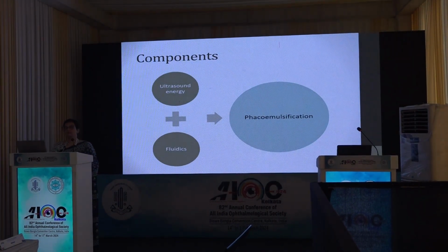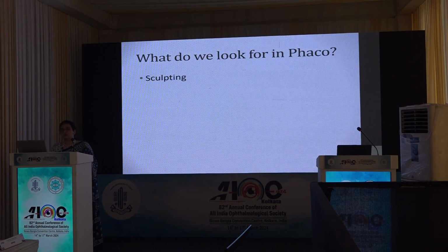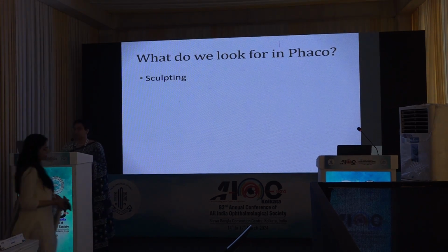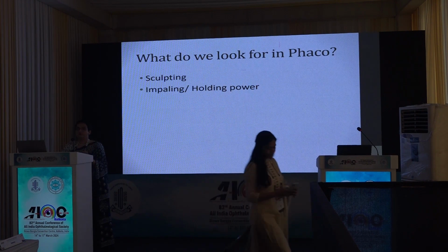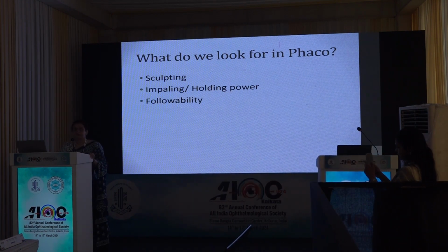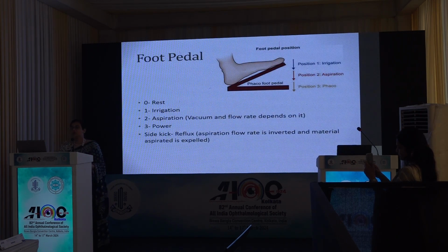I'll be presenting about the basics of phacodynamics. So what does phacoemulsification consist of? It consists of the ultrasound energy, which gives the power, and the fluidic system for the process to occur smoothly. Now what do we look for in phaco? We look for the sculpting of the nucleus, the impaling or holding power of the phaco probe, the followability of the nuclear fragments which are created, and the chamber stability at the same time.